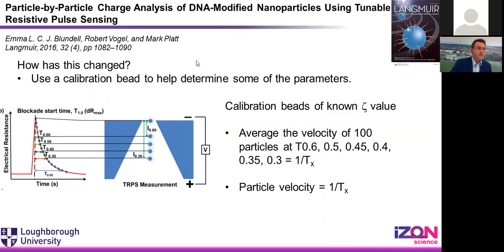I argue it's a slightly simpler method. The idea is that instead of having to calculate each of those individual contributions for the particle setup that you have, where you have to know the pore dimensions and calculate the fluidic flow and the electroosmotic flow, you can use a calibrant. You can measure the velocity of a calibration bead of a known zeta potential, and then relate the unknown particles you're interested in back to this calibrant and calculate their zeta potentials. So it's going to rely on the same concept that we showed before, where we look at the pulse.